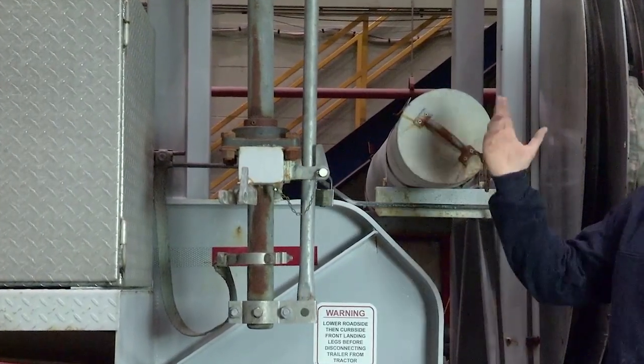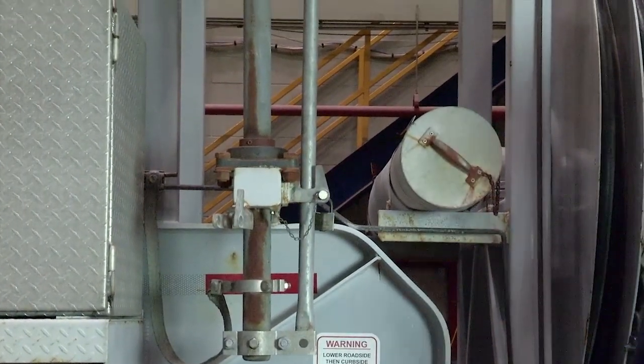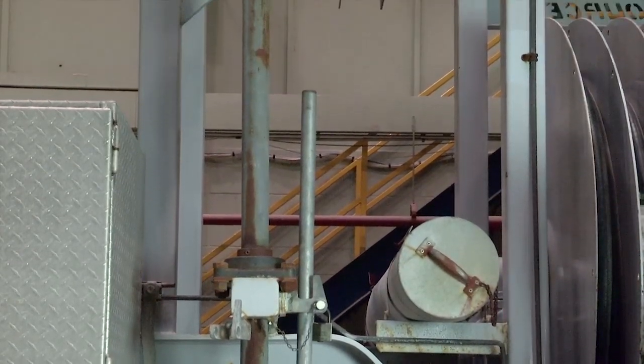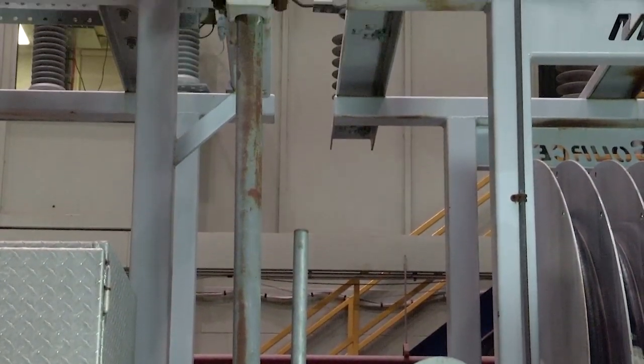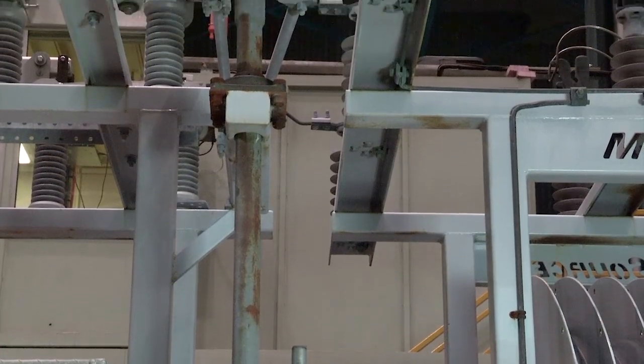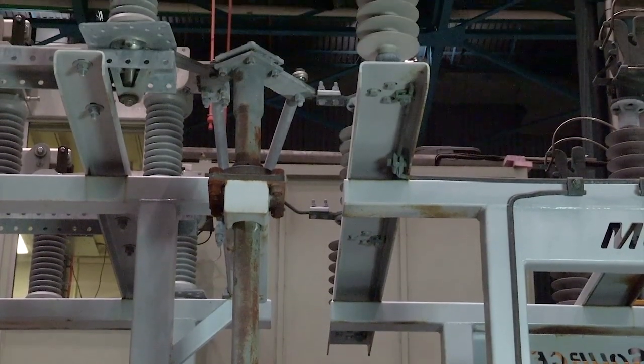And just as you go up the switch, just make sure that your typical overhaul, your insulators are good, no cracks. These ones are poly. Make sure every pivoting point, everything's greased, and you do a good overhaul on the switches.